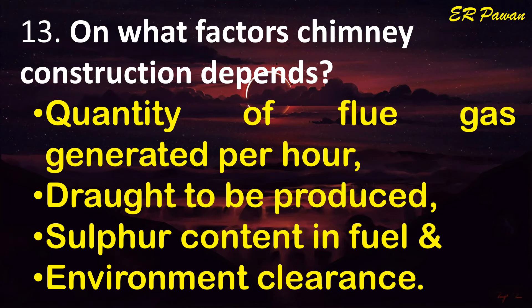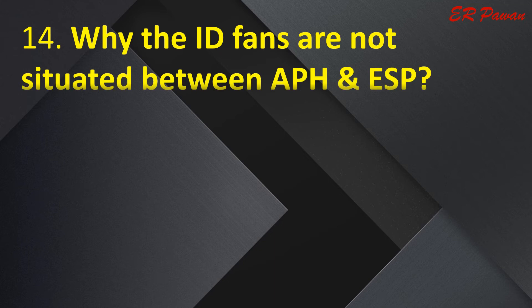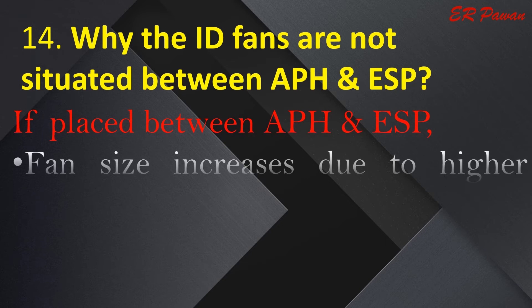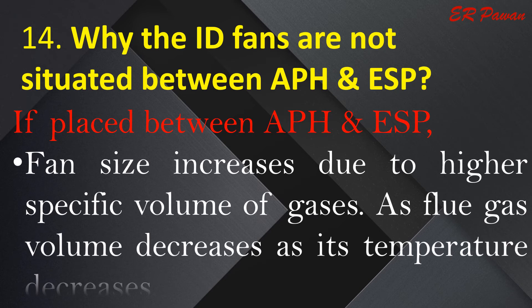Question 14: Why are ID fans not situated between the air preheater and electrostatic precipitators? If placed between the air preheater and electrostatic precipitators, fan size increases due to higher specific volume of gases, as flue gas volume decreases as its temperature decreases.